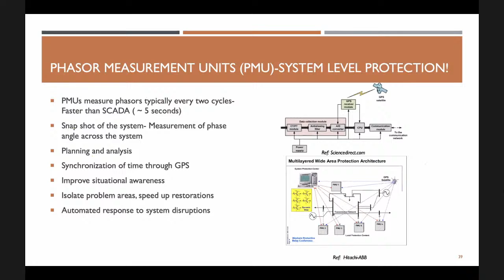I can use it for taking preventive action, because in the next slide, if you look at the right side picture, the horizontal axis is time and the vertical axis is the time it takes. You'll find that SCADA takes a few seconds to update itself. Protection relays have mostly been local all these years, so they take local information and trip within 20 to 30 milliseconds. There was a big gap between the SCADA measurement and operation control, and the protection's instantaneous tripping for equipment.